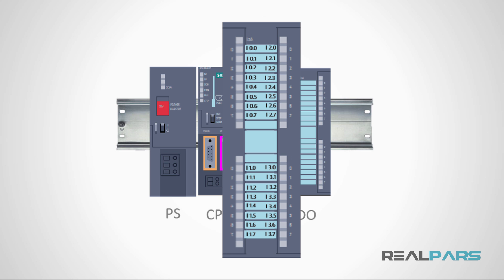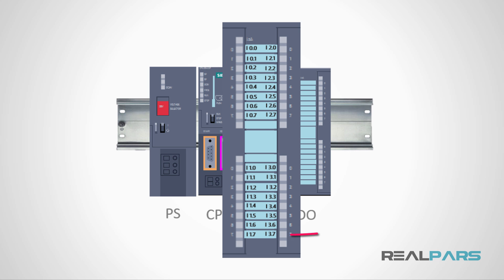Since the input addresses start at byte 0, the address for the first input of this module would be I0.0. Using that same model, the next input address for this module would be I0.1 and the next one would be I0.2. This continues all the way up to the last input address which is I3.7.